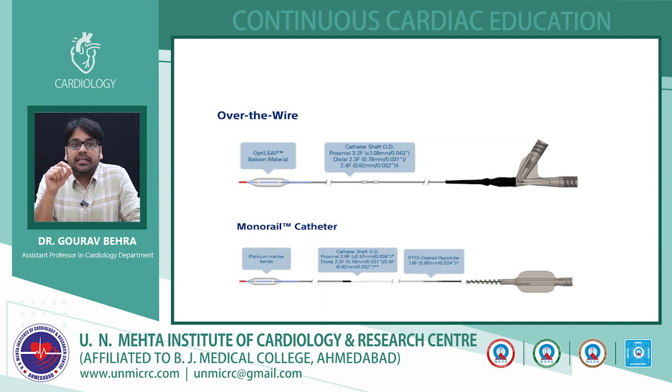The second, more advanced, is the monorail catheter. You can appreciate that there is only a single port in the distal connection. You attach the inflation cap to that port, and you can appreciate that initially there is a black marker in between. That part is the monorail system. So you can deploy the balloon very easily, and there are multiple instruments you can pass through it. So, monorail catheter and over-the-wire.